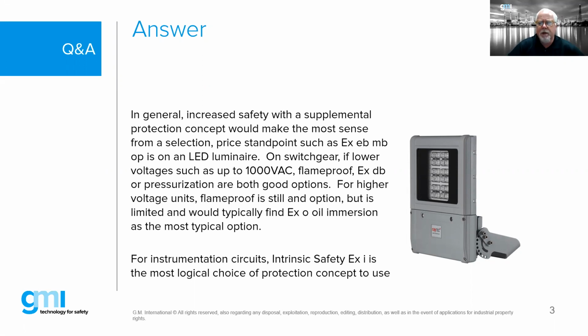When we get into switchgear, lower voltage up to 1,000 volts, usually flameproof or pressurization make really good sense. When we start getting above 1,000 volts AC, you're starting to get limited, but flameproof is still an option. We also would find in many cases, sometimes, oil immersion for extreme applications, but generally speaking, flameproof and increased safety are the real common protection concepts for power applications, for higher power applications.